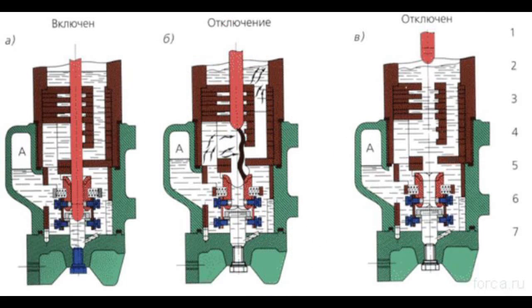The oil vapors partially decompose, producing hydrogen, ethylene, and methane. A gas bubble with huge pressure is formed within the range of the arc. When the contacts are broken, the arc is suppressed under the influence of quick cooling by gas and oil vapors.